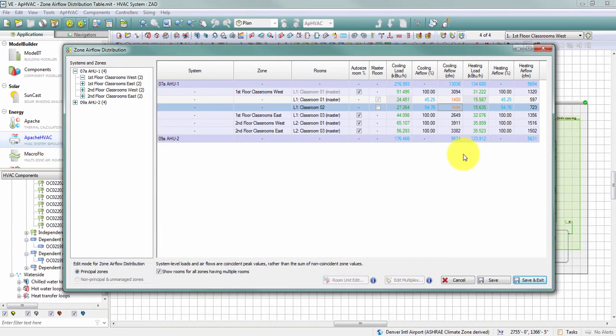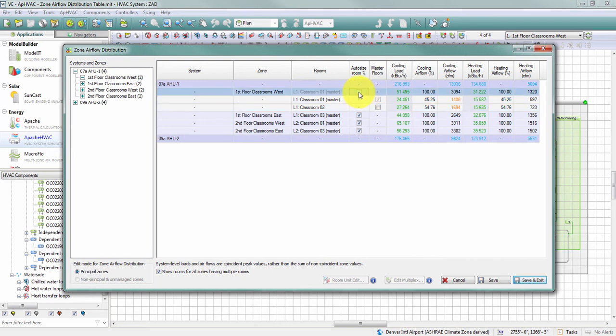After making manual changes to the airflow distribution, I want to pay attention to the Auto Size Room Percentage checkbox. The heating and cooling airflow percentages were auto-sized based on the relative load of the spaces. Since I've changed that distribution to roughly 45–55% rather than 48–52%, I'll uncheck this box. Once unchecked, the light blue airflow percentage numbers turn black, indicating they will not auto-size when system loads are run, and these manual edits will be retained.